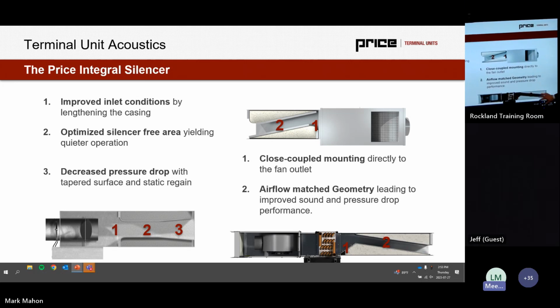When we look at this on fan powered units and fan coils, really the big thing we try to do is airflow match the geometry. So in this case, a double width, double inlet motor blower assembly is going to throw air down kind of like a water wheel. It's very directional. And so if we match the baffles with that directionality, we'll get lower pressure drop and better performance. The size 50 FDC, which is one of our products, its airflow range actually goes up when you put a silencer on it because it's better than an open duct condition. We don't catalog it though because it would just confuse everybody. So we keep it the same, but it actually is a better condition than an open ductwork.